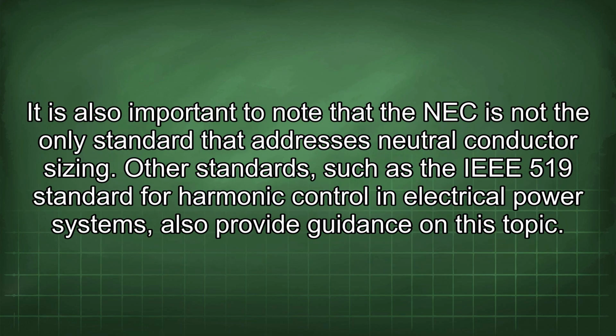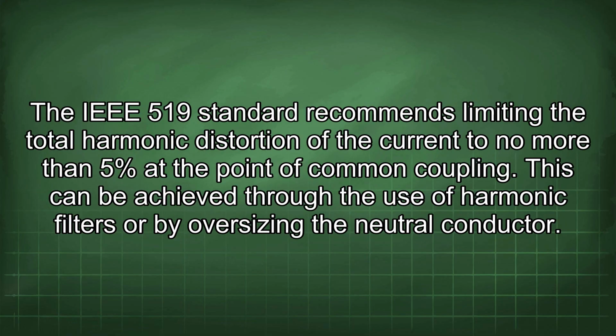It is also important to note that the NEC is not the only standard that addresses neutral conductor sizing. Other standards, such as the IEEE 519 standard for harmonic control in electrical power systems, also provide guidance on this topic. The IEEE 519 standard recommends limiting the total harmonic distortion of the current to no more than 5% at the point of common coupling. This can be achieved through the use of harmonic filters or by oversizing the neutral conductor.